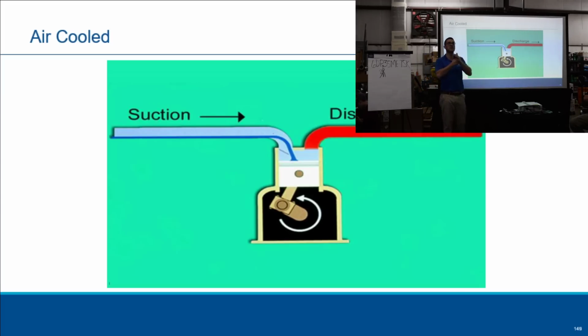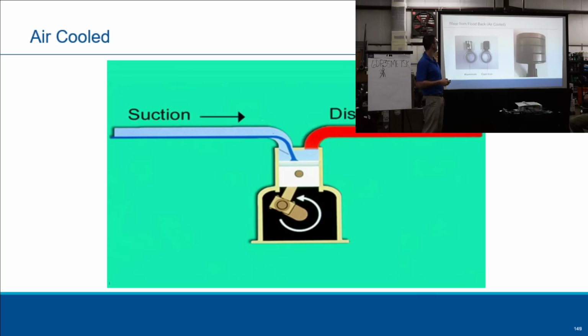Air cooled: you have liquid refrigerant coming right into the head, and then what happens? What are you trying to do inside that? You're trying to compress, and what does that cause? A blown piston, which we call a slug. It could be liquid or could be oil, but we're talking about flood back. Then you look inside that cylinder and you'll see up and down wear. And if it's a larger one, you'll see up and down wear in the cylinders of air-cooled compressors, because that liquid refrigerant is going right inside the head and washing out the oil.